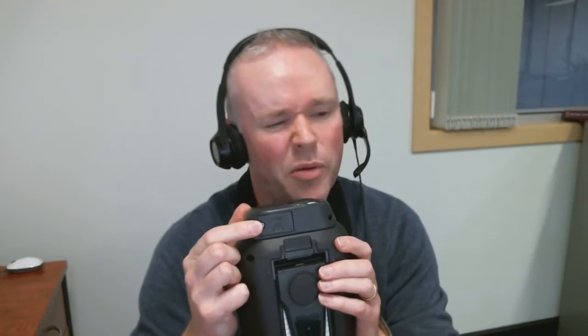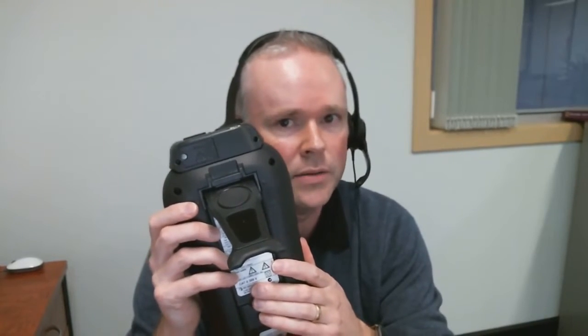Apart from that, the other things people need to know about are the fuses. So there's 2 little ceramic fuses that go in the back there. They're both 16 amp fuses. If you can't do a leakage test for whatever reason, it could be that you've blown a fuse. All you do is unscrew the cover, pop the fuse in, and the leakage testing and the RCD testing will work. The other part is there's a battery cover there, and that's where your 6 rechargeable batteries are located.